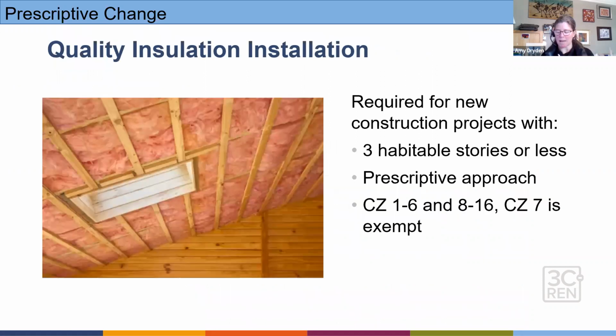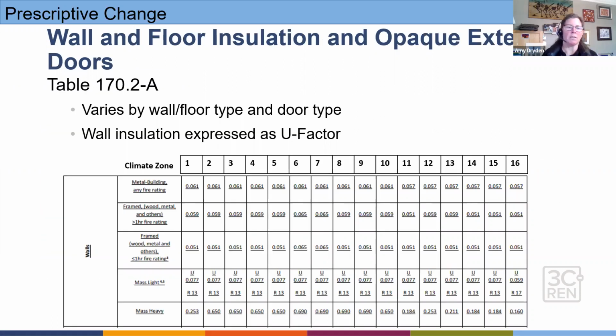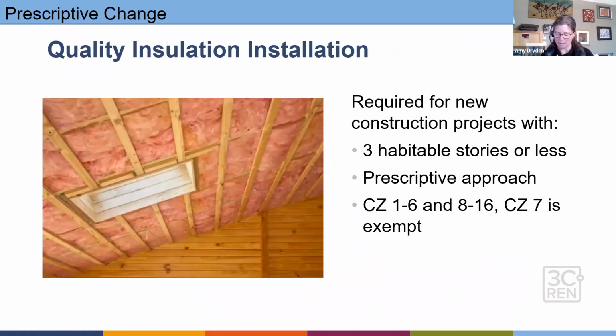So we have a maximum U factor, and then you can see it's a minimum. Like if we look at these walls here, and we're looking at either the light or the heavy mass, the two lower rows, that's a maximum U factor and minimum R value, right? So R13 is my minimum, and my maximum U factor is 0.077. So each of them have that min and max. Okay, go ahead, Lauren.